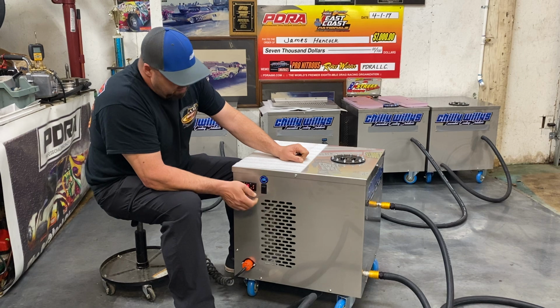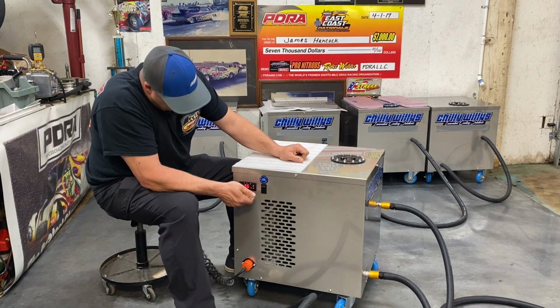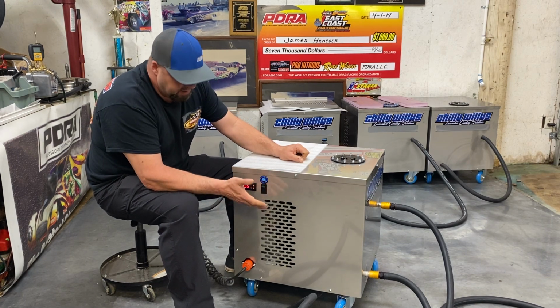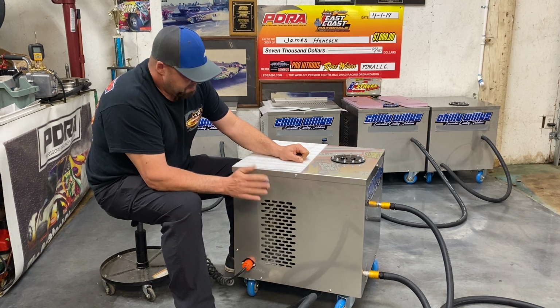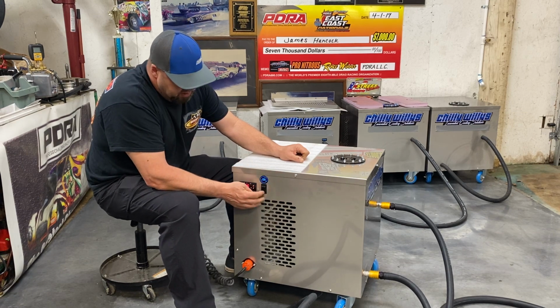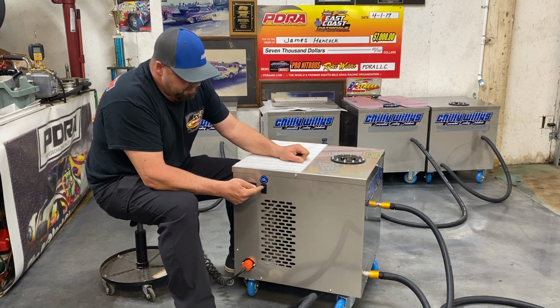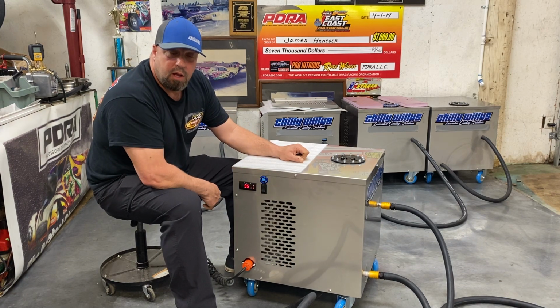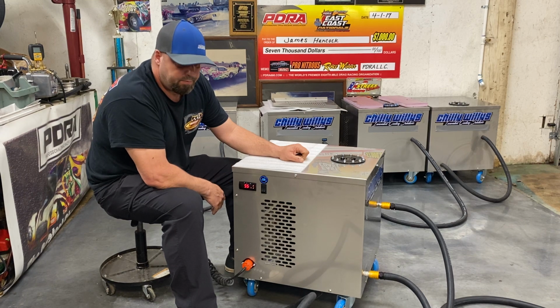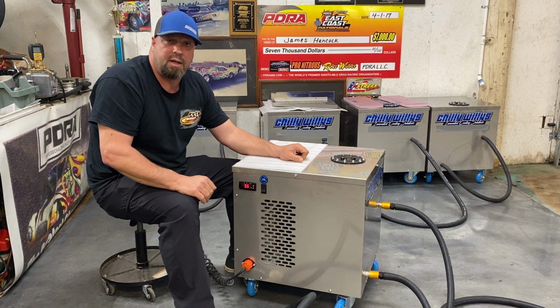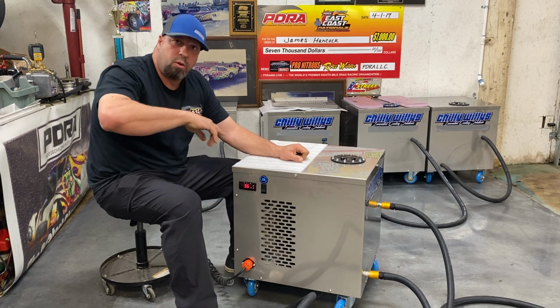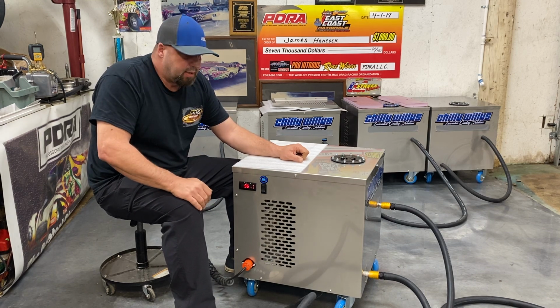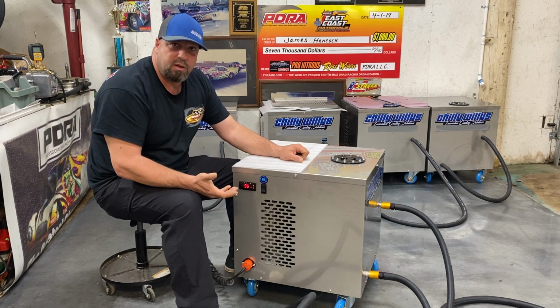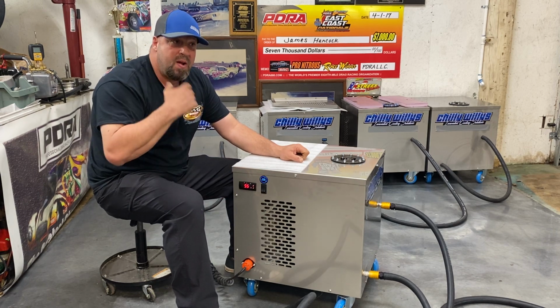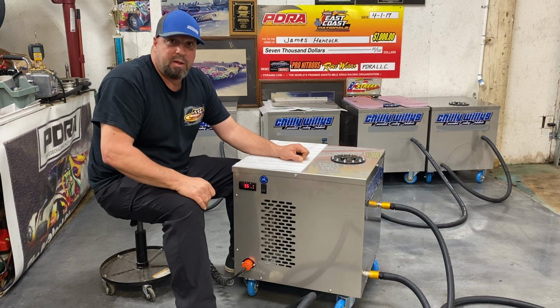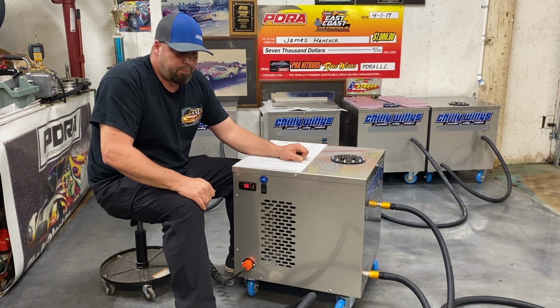Another question we commonly get phone calls on is, what does the switch do? Right now, this machine is satisfied, so it's brought down to 55 degrees, it's at temperature. Everything's cut off, and the switch is down. If the switch was left up, the circulating pump continues to run, you can hear it humming now. I always leave mine running, I always want the water to circulate. The reason being is if it doesn't, if you have to switch down and the compressor comes on and you're out making a lap and the water's not circulating, the water can freeze up on the inside and the chiller can't properly do its job.